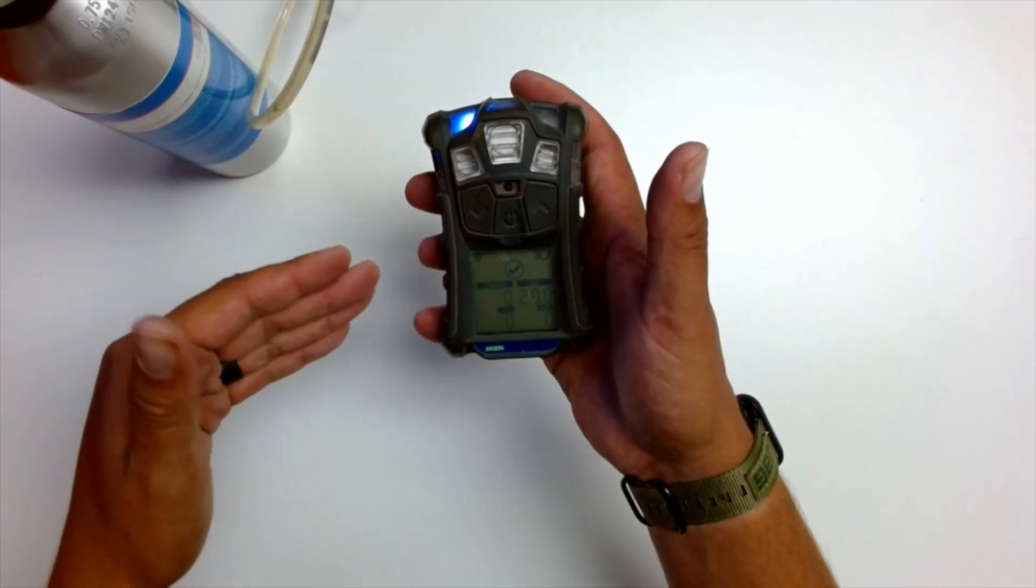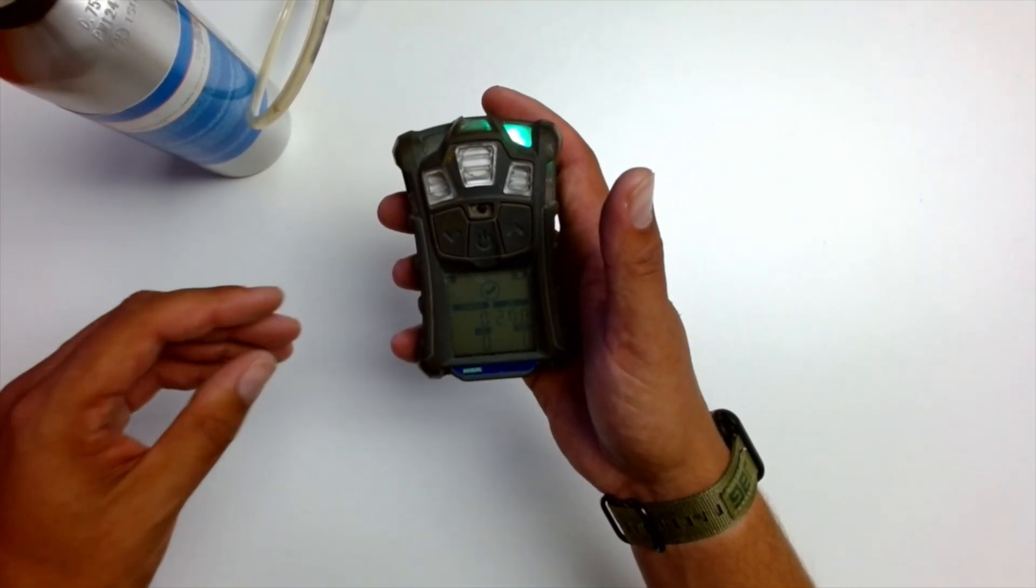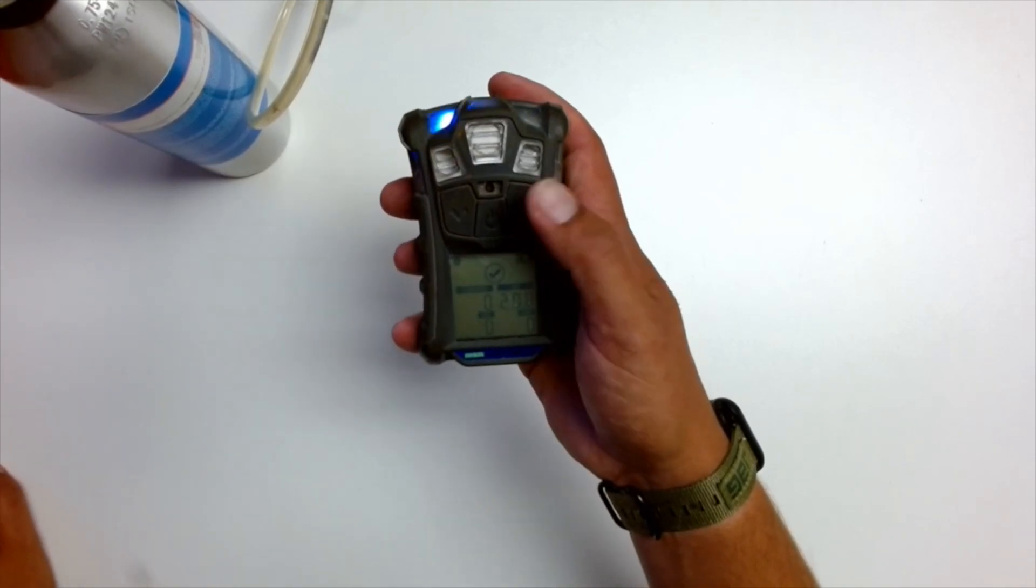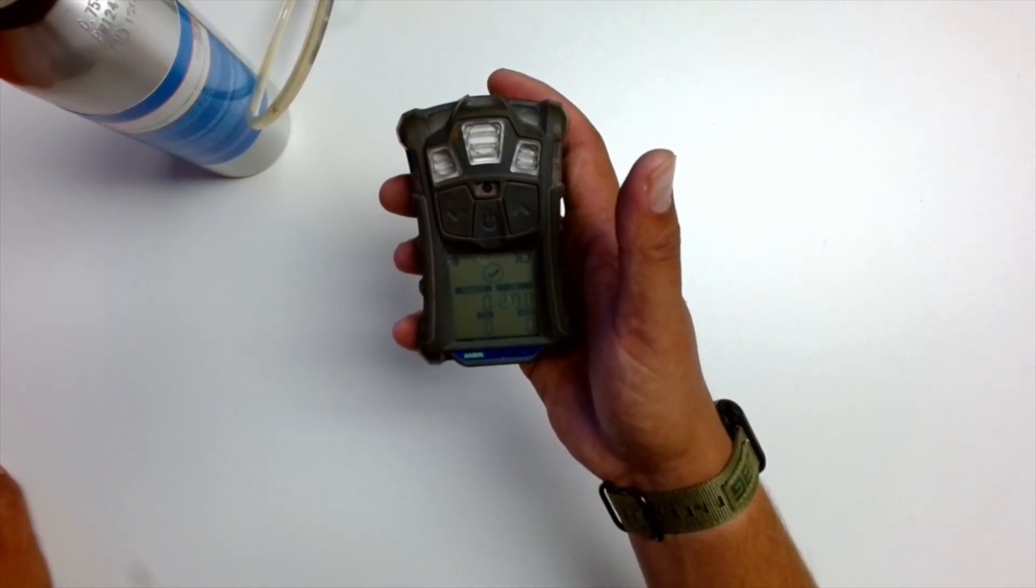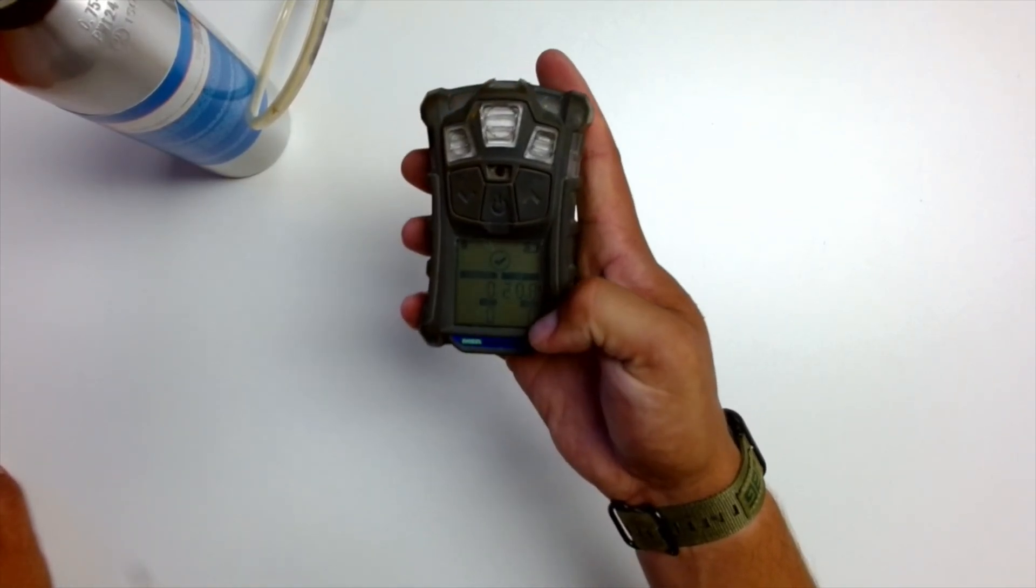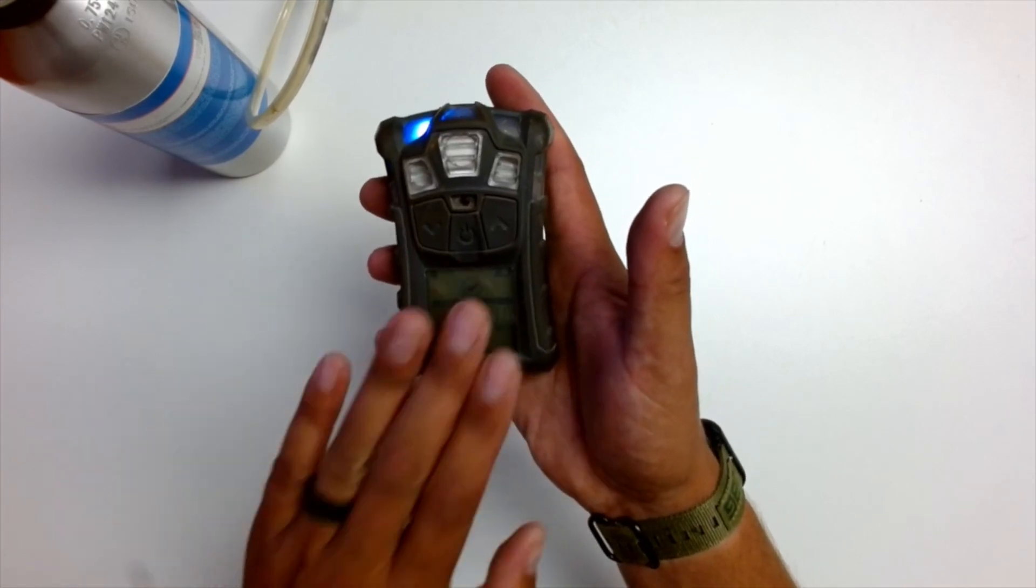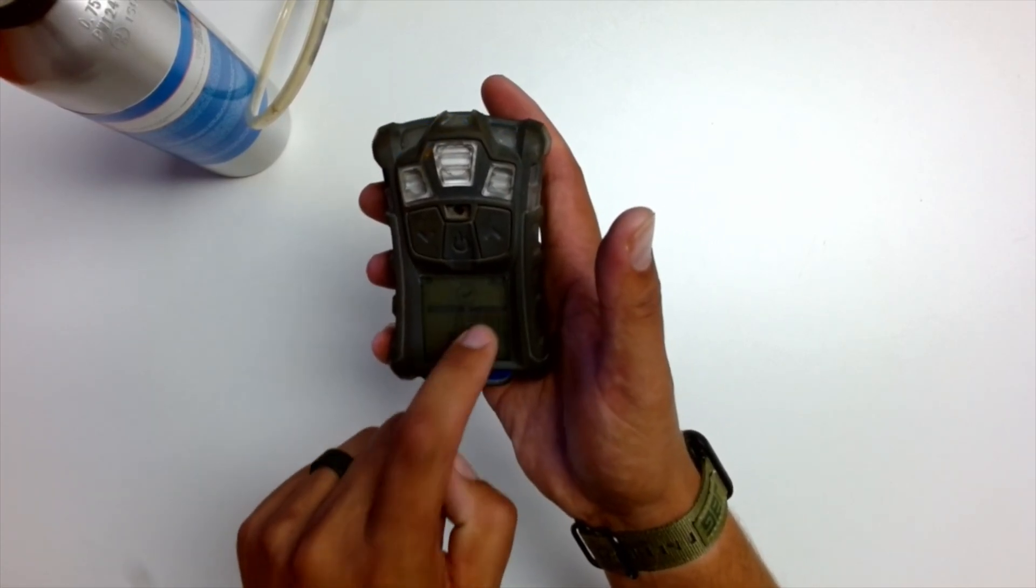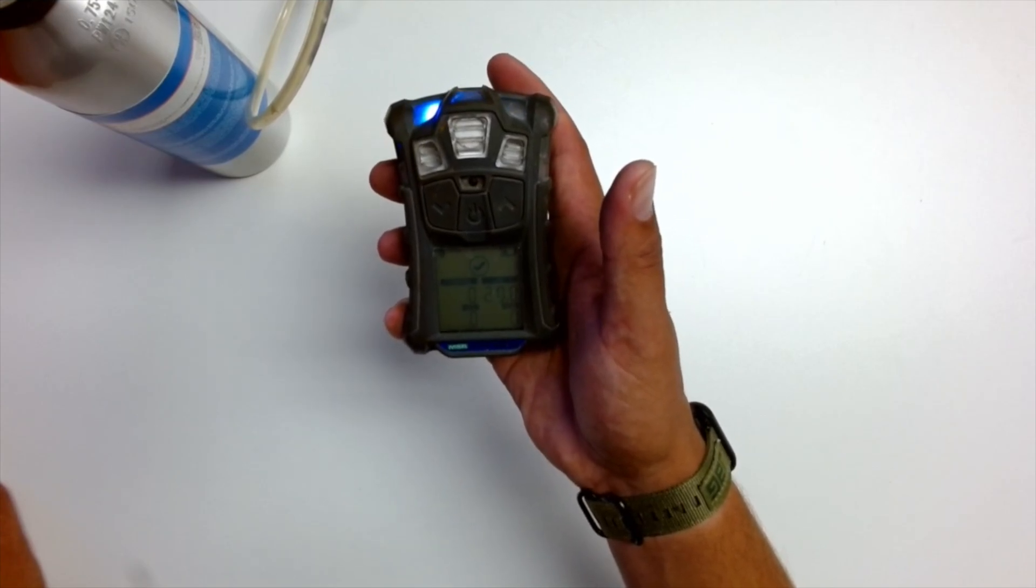So because gas was flowing through the monitor itself, basically all you want to do is, if you hit the up arrow at the end of that bump test, it will reset your alarm as well. Those values come back down to zero, but always make sure your values do come to zero and your O2 does come to 20.8.